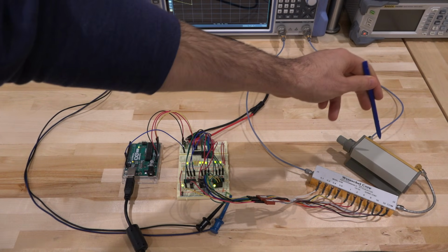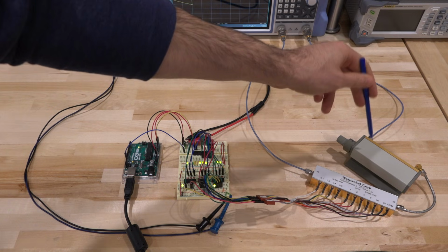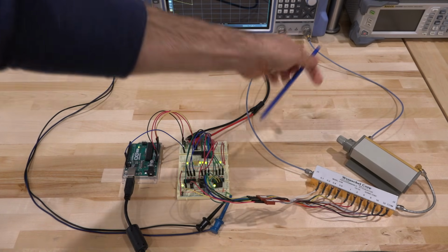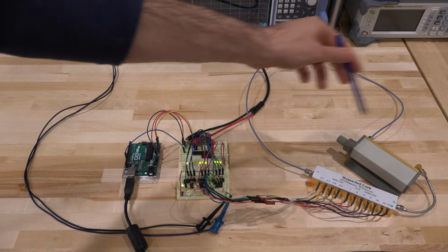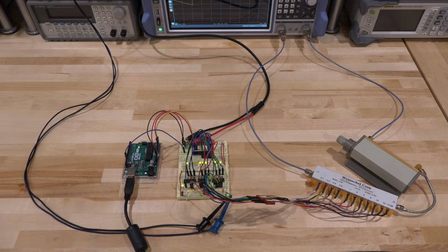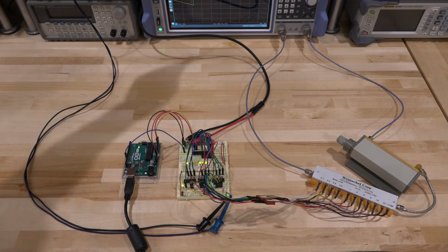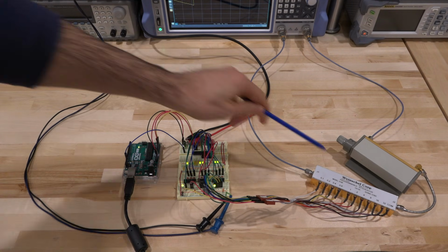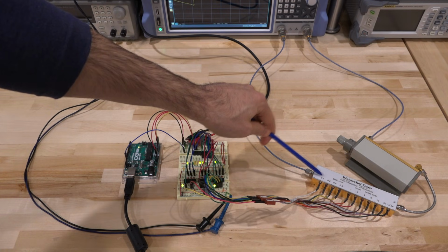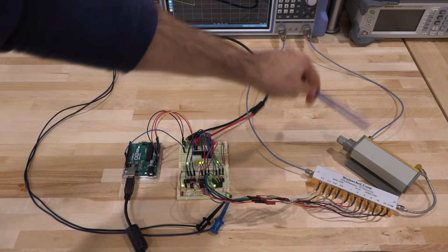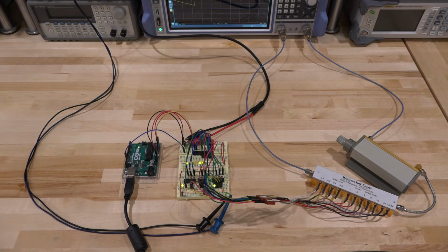So I also have a mechanical attenuator here, which is controlled manually. You can adjust it, and it can go from 0 to 70 dB. So in combination, you have a huge range of attenuation that you can apply. So we're going to take a look at that combination. So right now it's running, and port 1 of the network analyzer is connected to port 1 of the attenuator, which then is cascaded with the other one and then returns to port 2. So we should be able to do this.